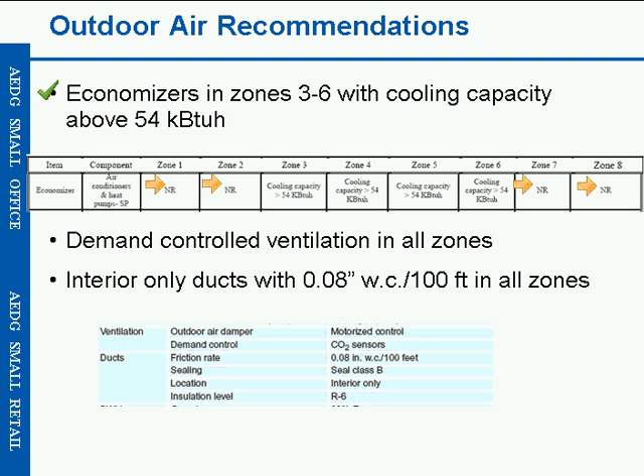Outdoor air is controlled based on CO2 for all climate zones, for both the small office and small retail. And there are also various recommendations for interior duct design, 0.08 inches per 100 feet of ductwork. You can see an example of what that table looks like in each of the design guides below here. For ventilation control, a motorized damper is recommended. Again, demand control ventilation, and then details on duct design for each climate zone are provided.